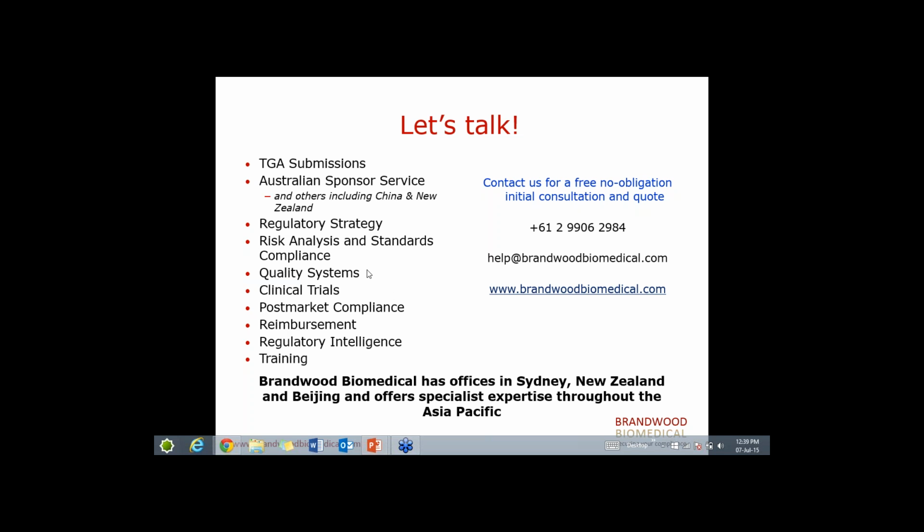Okay, the next question I've got here: how long does it take to get TGA approval if you have a CE certificate? With the timelines, there's no distinct answer, but it is a much quicker process than going through TGA. If you go through TGA conformity assessment, there is a lot of time and cost involved. As I mentioned before, TGA have limited resources in their devices area, so there's a lot of timeline involved. If you have a CE certificate, it is a much quicker process, but when we say quick, again, it depends on the resources of TGA.